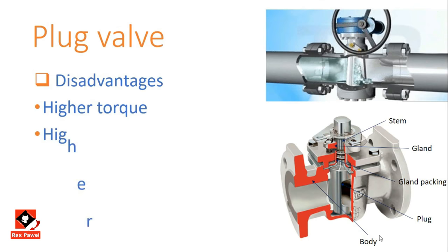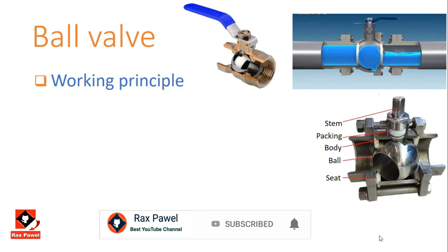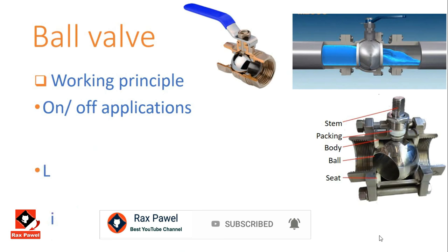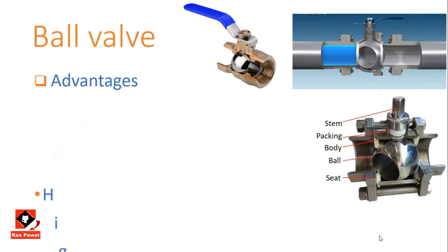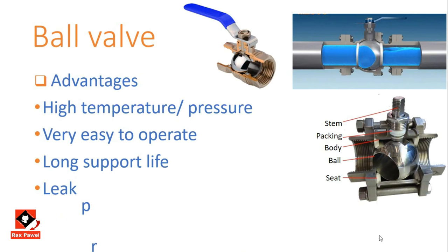The working principle of the ball valve is very similar to the plug valve. The seat matching the ball is circular, so seating stress is circumferentially uniform. The seats are usually made of polytetrafluoroethylene (PTFE), which is inert to all chemicals and has a low coefficient of friction. The valve is used only for on/off applications dealing with both liquids and gases. Ball valves can be divided into several types according to the way the ball is mounted and bore type. Advantages: it handles high temperature and high pressure applications, is very easy and quick to operate, and gives long service life and leak-proof performance.